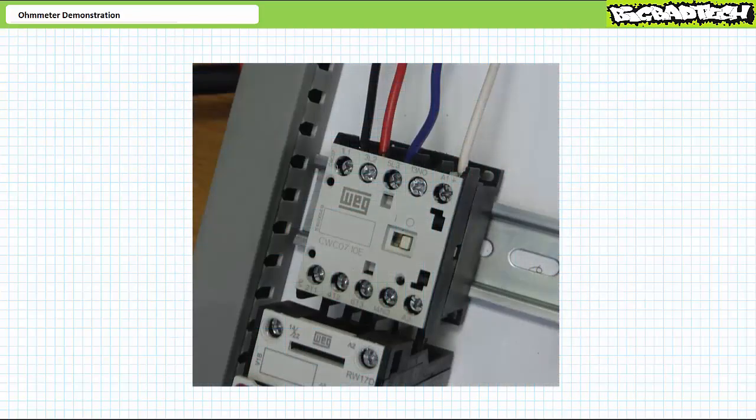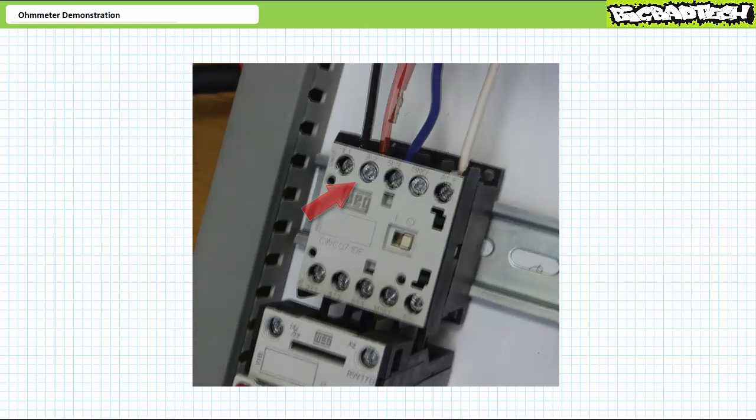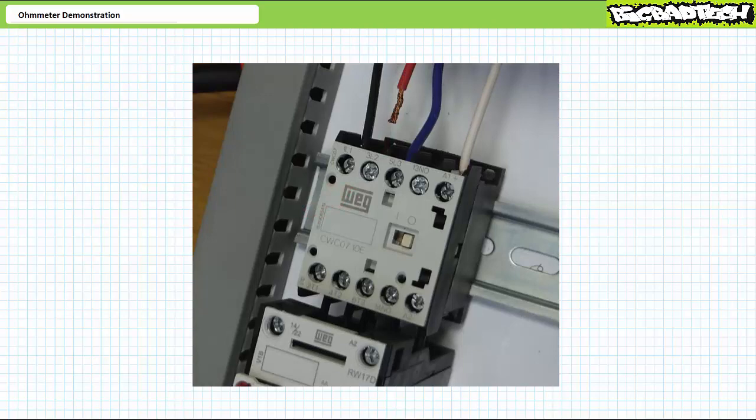Here's an example of a contactor, a type of heavy-duty electrical switch with a false connection on one of the three phases in a three-phase AC system. It might look like it's connected, however close visual inspection of the system shows that one of the screws is not tight all the way down, and the wire isn't making a positive connection, but rather dangling around out in space. The loss of a single phase results in the motor making an unusual growling sound, failing to rotate, and the overload element eventually disabling the system.